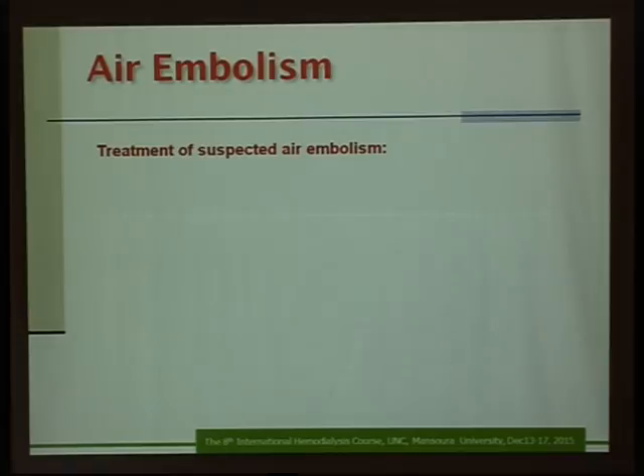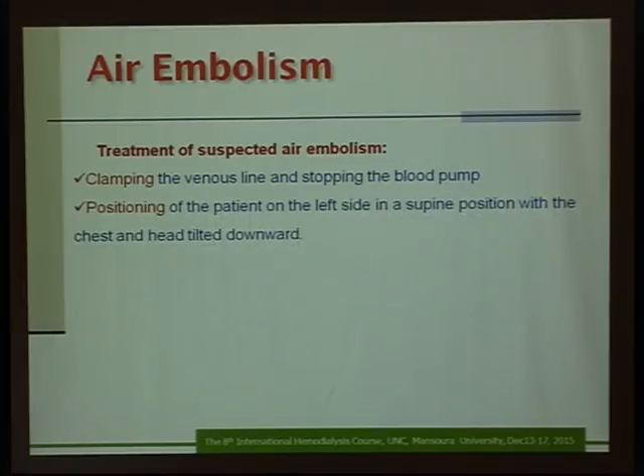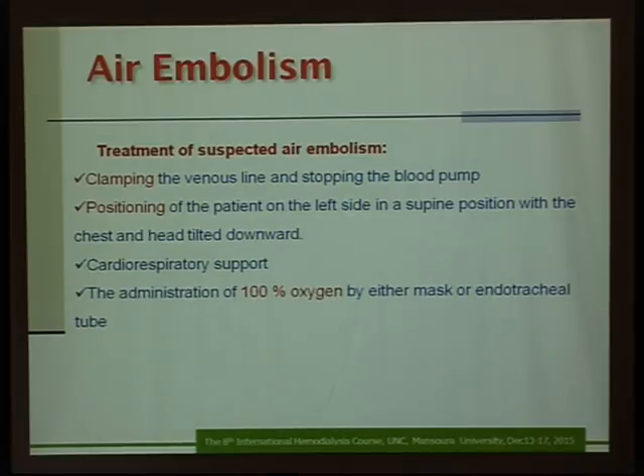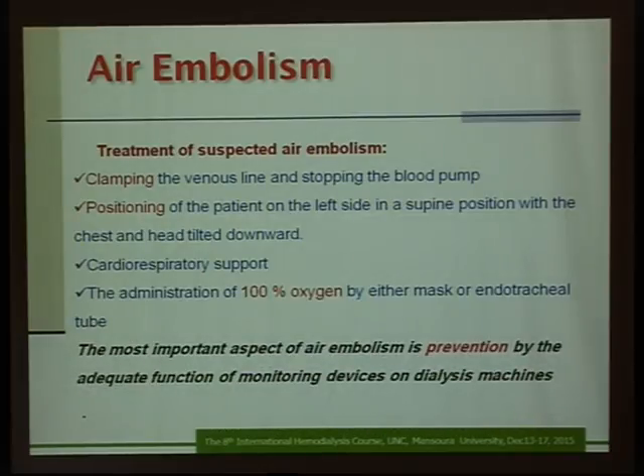How to treat such a catastrophe? Number one, clamp the venous line and stop the blood pump. Then, position the patient on the left side in the Trendelenburg position with his head tilted downwards. Cardiorespiratory support should be available, with administration of 100% oxygen by either mask or endotracheal tube. And the most important aspect of air embolism is prevention by adequate function of the monitoring devices and alarms in the dialysis machine.